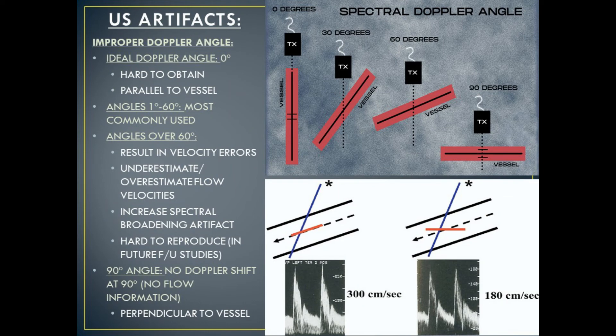Next, let's talk about ultrasound artifacts that occur due to improper Doppler angle. An ideal Doppler angle is 0 degrees — an angle parallel to the vessel — however, this is extremely hard to obtain. Because of that, angles of 1 to 60 degrees are most commonly used. When the angle is over 60 degrees, it results in velocity errors that underestimate or overestimate flow velocities, and they increase spectral broadening artifacts. They are also extremely hard to reproduce in future follow-up studies. When a Doppler angle of 90 degrees is used, no Doppler shift occurs, so there is no flow information. 90 degrees is perpendicular to the vessel.